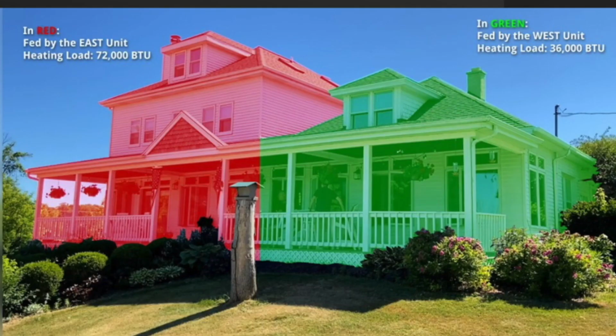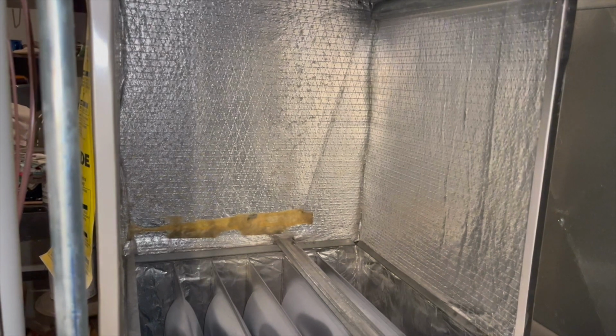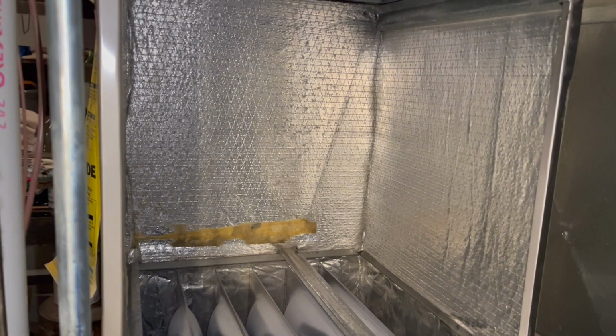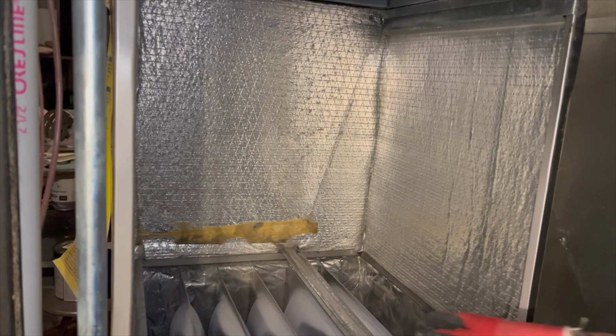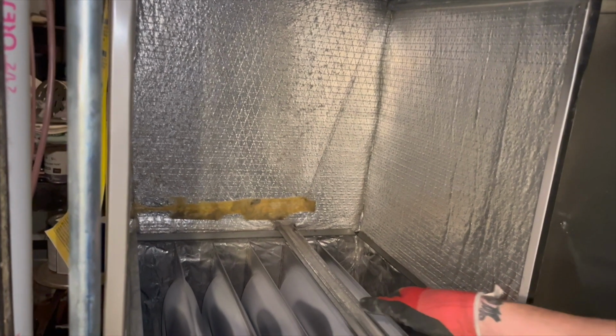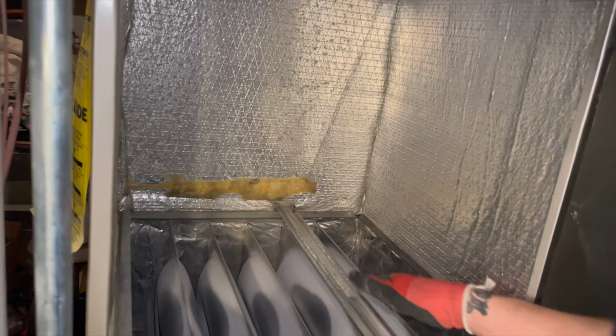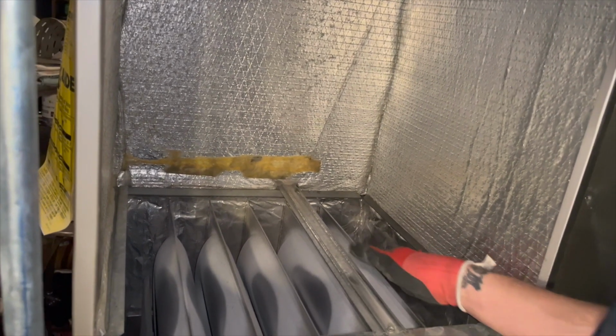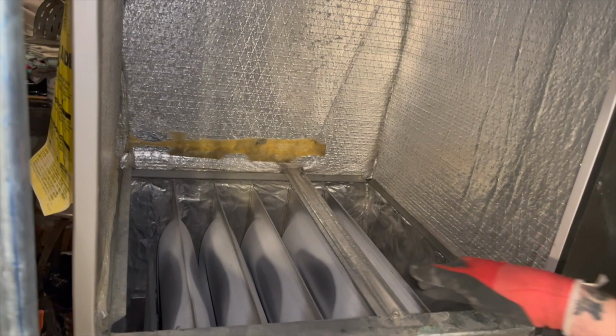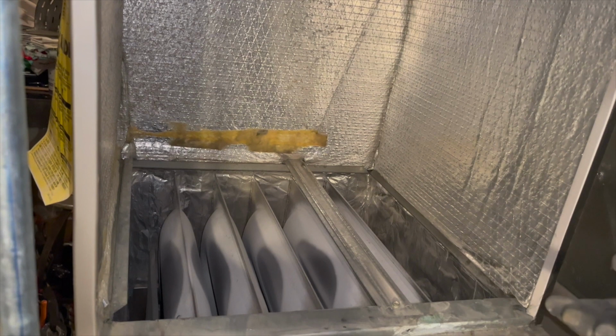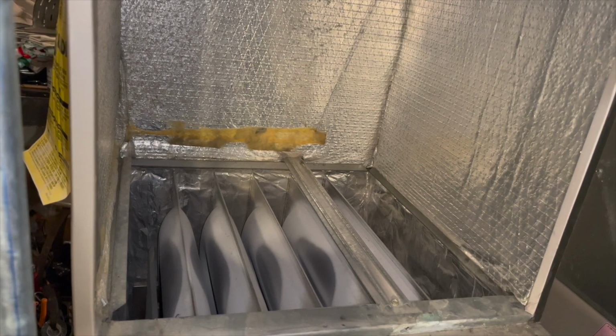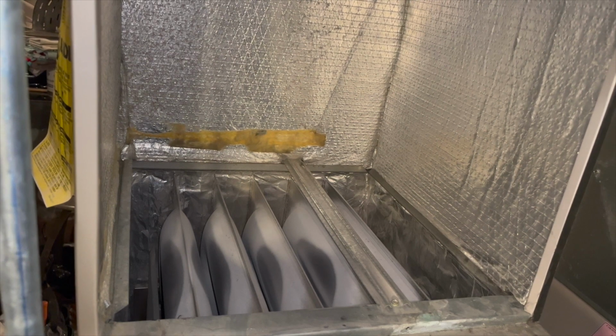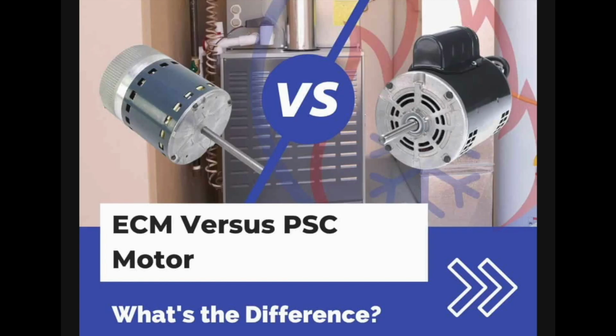Finally, here are a few recommendations for you if you're considering a heat pump retrofit. Number one, make sure your contractor performs a load calculation on your property, especially if you're going to use your heat pump at lower temperatures. Number two, make sure you inspect your existing furnace, particularly the secondary heat exchanger. There's no point in retrofitting a failing furnace with a new heat pump. Of course, your contractor should be able to help you determine whether or not your secondary heat exchanger has failed. Number three, for this dual fuel rebate, you will need to make sure that your existing furnace has an electronically commutated EC motor. Otherwise, you won't comply with the rebate requirements.